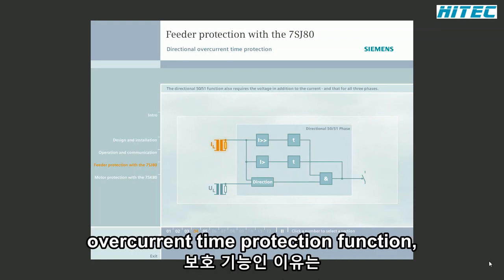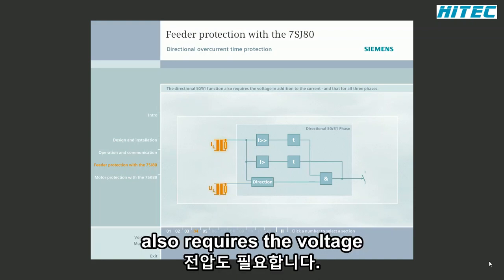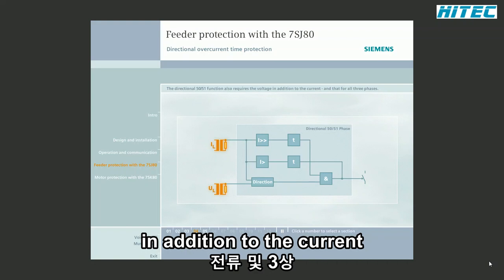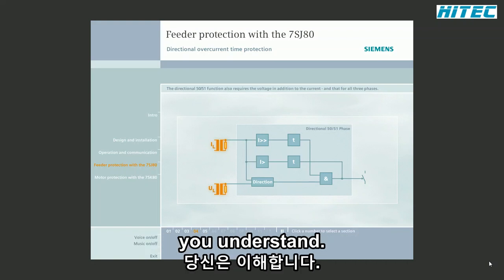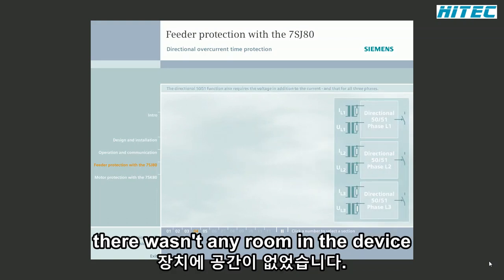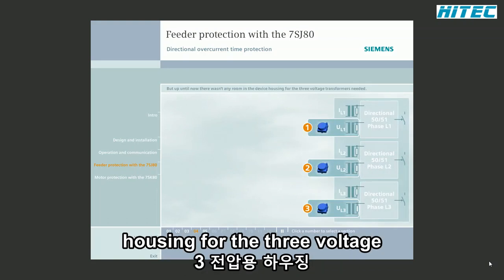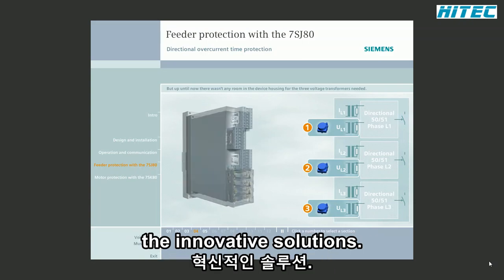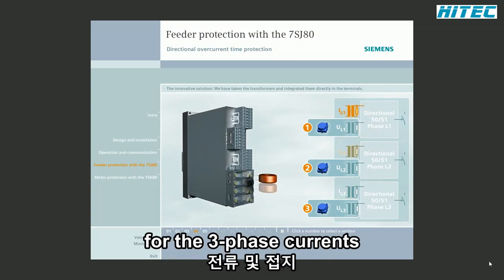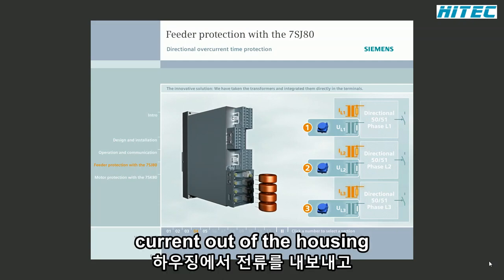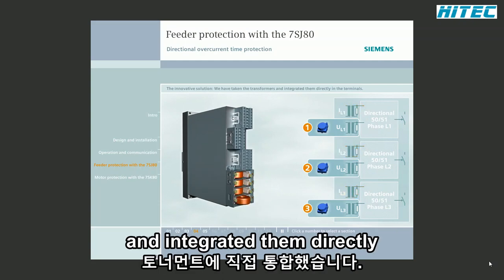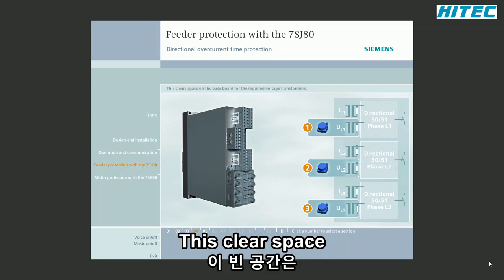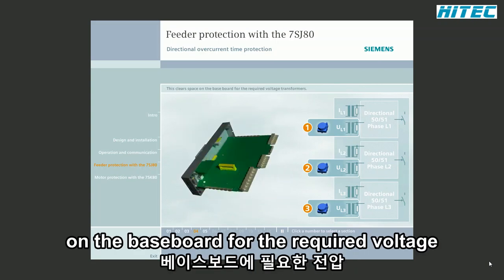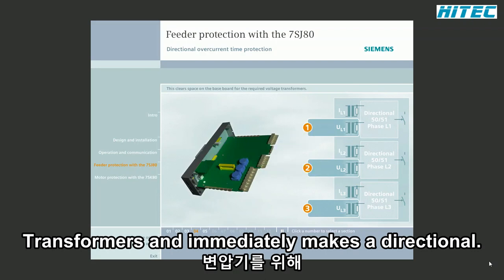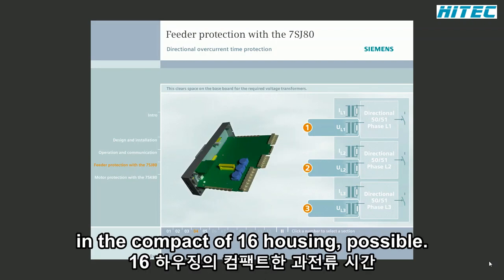The directional overcurrent time protection function also requires the voltage in addition to the current, and that for all 3 phases, you understand. But up until now, there wasn't any room in the device housing for the 3 voltage transformers needed for this. The innovative solution: we have taken the transformers for the 3 phase currents and the ground current out of the housing and integrated them directly in the terminals. This clears space on the baseboard for the required voltage transformers and immediately makes a directional overcurrent time protection in the compact 1/6 housing possible.